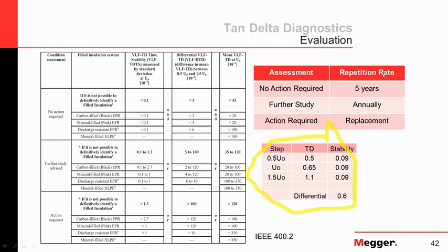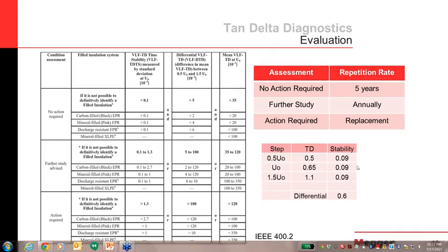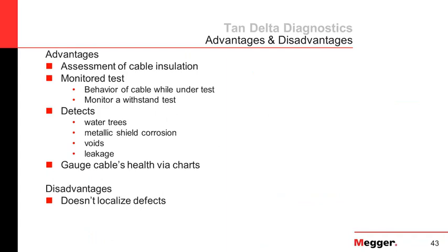When running a tan delta test, you get a really good assessment of your cable insulation. This test is monitored — at each voltage level, you can see how the cable is behaving. You can even use the tan delta test to monitor a withstand test, getting insight rather than doing a completely blind test. Tan delta is used to detect water trees, metallic shield corrosion, voids, and anything that causes leakage current. You can gauge cable health using the IEEE charts. Unfortunately, tan delta diagnostics does not localize any of your defects.